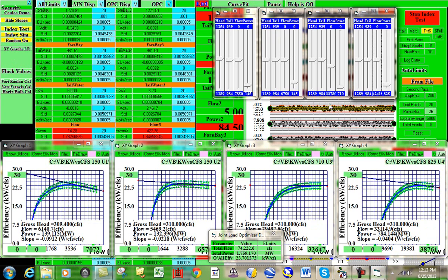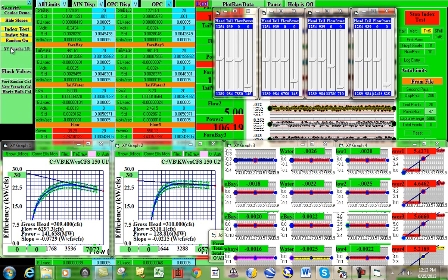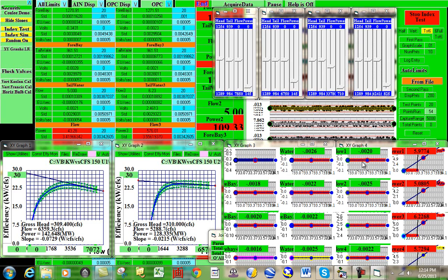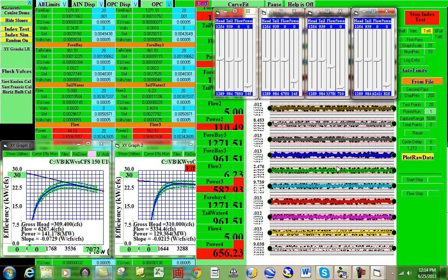Only now what's happening is we're measuring the analog inputs at 1,000 samples per second. We're taking 200 samples. We're taking the standard deviation and linear regression and plotting those on this little form. And then using the first set of limits, this lower 3 are the first set of limits for the first pass data. And then I'll click on the lower right. And then as the data collects, it takes the first pass samples and does a standard deviation on those and then plots them in the second set of forms. And when I click on the reset, it'll set everything to 0.